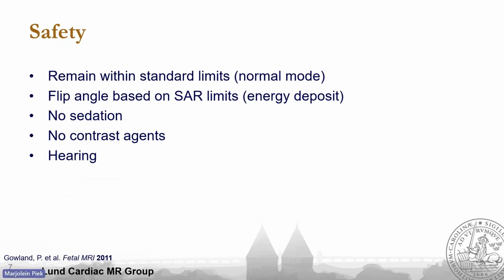And then for safety, that's the question we get a lot, mainly from the volunteers and the patients. So what we do is to remain within standard limits when we're scanning. And on the scanner, this is called normal mode. And what it actually does partially is to limit the energy deposition in the body, which is called the SAR limit. This also means that we have to reduce our flip angles. We do not use sedation nor contrast agents.